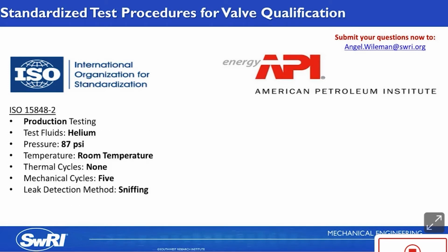ISO 15848-2 is very similar, but it's -2, it's the second part, and it's production testing of the valves. So this is where you take one valve from a production lot per valve type, class, and size, and you're qualifying that individual valve, not testing the design. It's a requirement that all the valves tested are already qualified to ISO 15848-1.